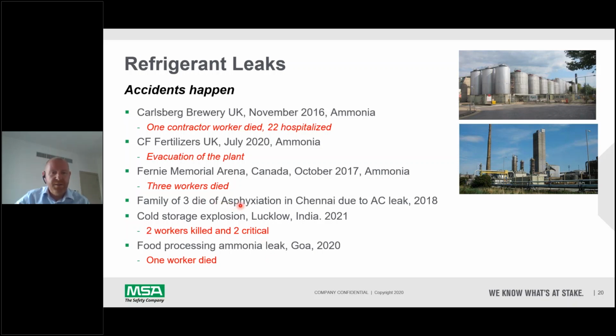Unfortunately, there was a death of 3 people due to asphyxiation in Chennai due to a leak from an air conditioning system. So this must have leaked into a small enclosed room, and the refrigerants are heavier than air except for ammonia, so they will go to the floor where people are sleeping. So this is one of the dangers and why leak detection is necessary for safety.